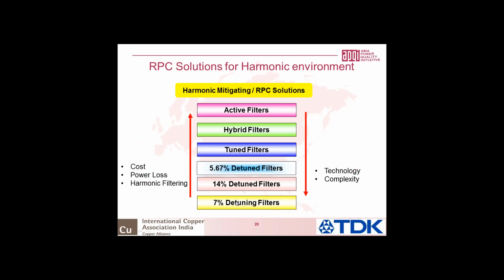As I said, you have the detuned banks, which are 7 or 14%. Then we have partially tuned banks, passive tuned filters, hybrid filters, which are a combination of passive and active filters, and then active filters. As you go from bottom to top, the cost per ampere or cost per kVAR goes up. The power loss goes up. For example, if you take a detuned LC filter, the power efficiency could be 99.2 or 99.3%, whereas when you take an active filter, the efficiency could be 96, 97 or 98%. But as you go up, the harmonic filtering efficiency goes up. Similarly, when you go from top to bottom, the technology and complexity come down.